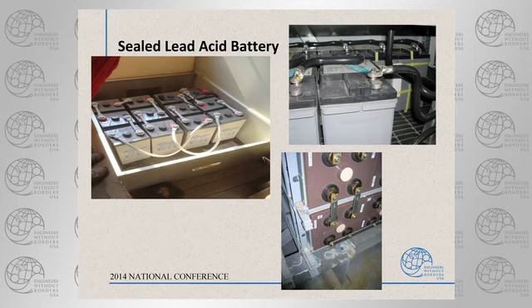Over here, those look like they're flooded lead acid product. And from the picture, I would have assumed they were flooded. But when you zoom in, they're actually sealed. Those are valved vents, and they will release under pressure, but they're not removable to service the battery. Down here, these are 2-volt sealed cell. Well, semi-sealed, you see that? That tells me the seal wasn't too successful. The jar to cover seal probably leaked here. These are in a telecommunications plant. These batteries are about 12 inches square. They're about 30 inches deep, 1,400 amp hour at 2 volts.